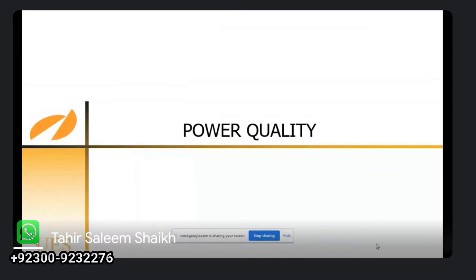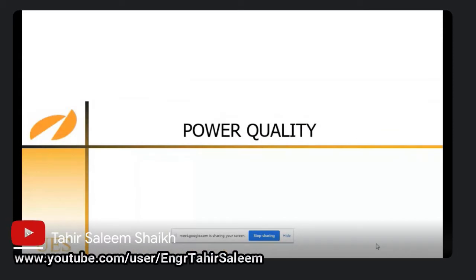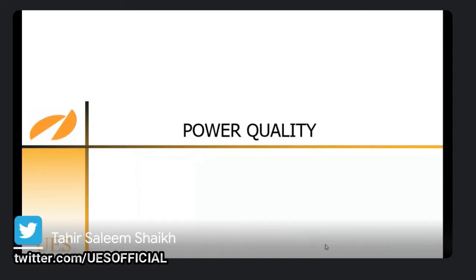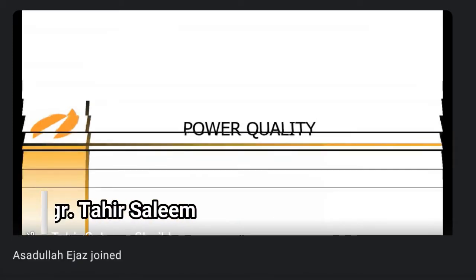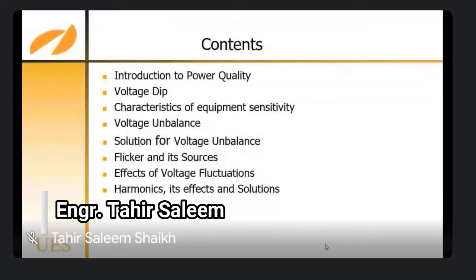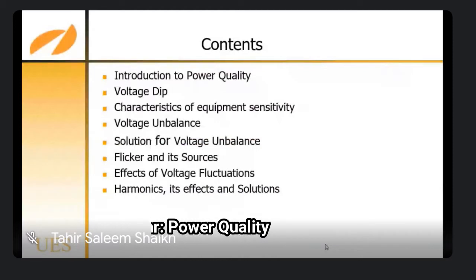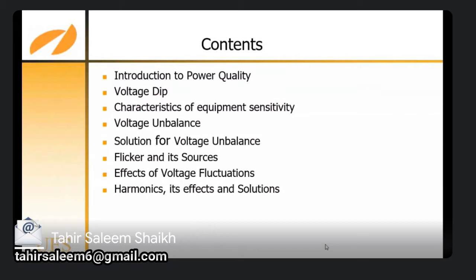I have so many examples with me. I have done so many power quality audits in process industries, and I know that there is a lot of problem if you are using UPS, computers, VFD. These are all called non-linear loads, and non-linear loads need some special considerations in designing. So let's start. I will discuss an introduction to power quality, then voltage dip, characteristics of equipment sensitivity, voltage imbalance, solutions for voltage imbalance, flicker and its sources, effects of voltage fluctuation, and harmonics and its effect and solution. That is also very important. This is the most important in power quality: harmonics, the impact of harmonics.